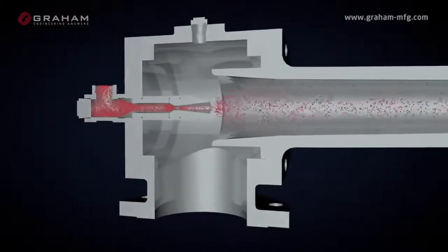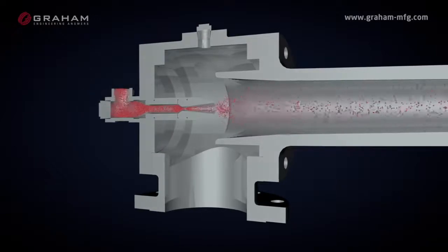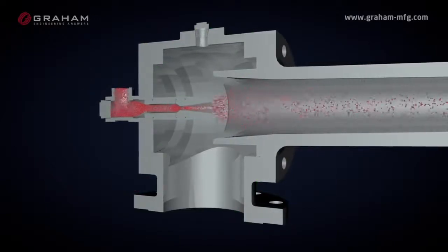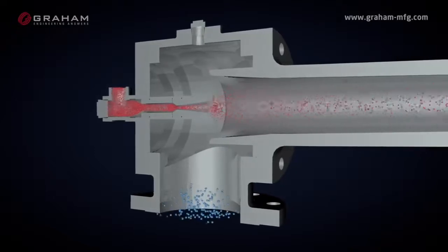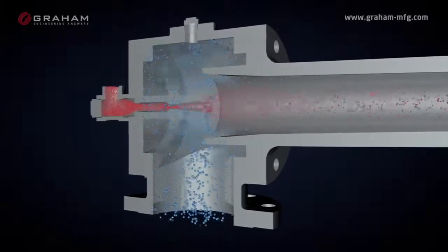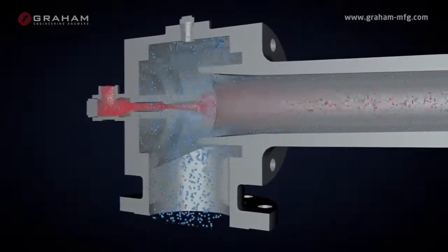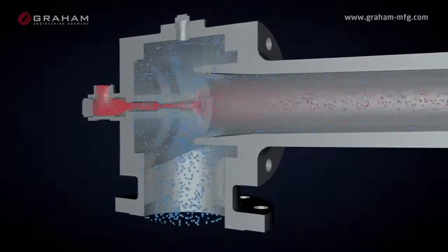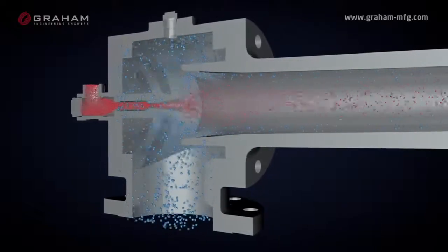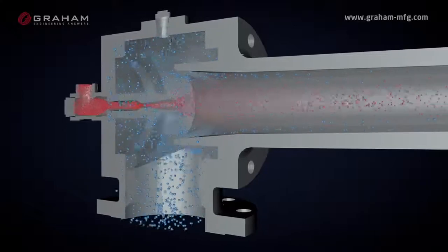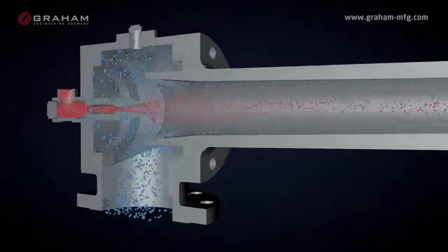Housing the motive nozzle is the third component: the suction chamber. This is the mechanical connection between the nozzle and the rest of the ejector. The high velocity motive stream mixes and entrains the processed gases in the suction chamber. Momentum is transferred from the high velocity motive stream to the suction load gases, accelerating the suction load gases and, consequently, decelerating the motive gas to a new mixture velocity.